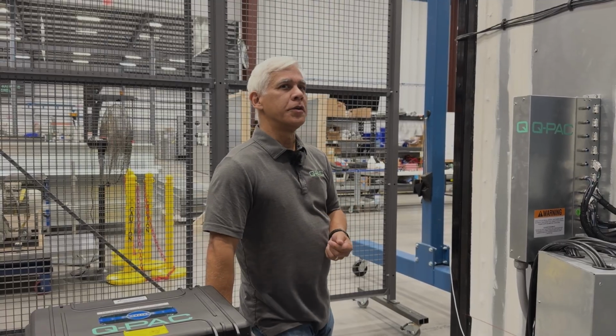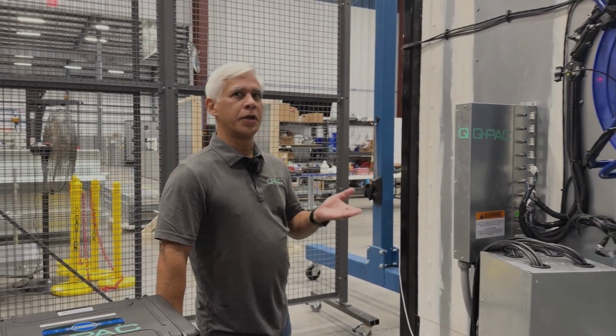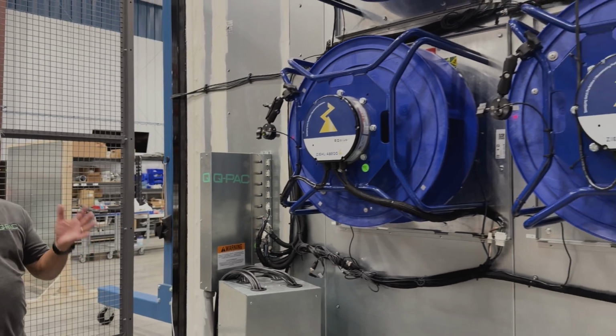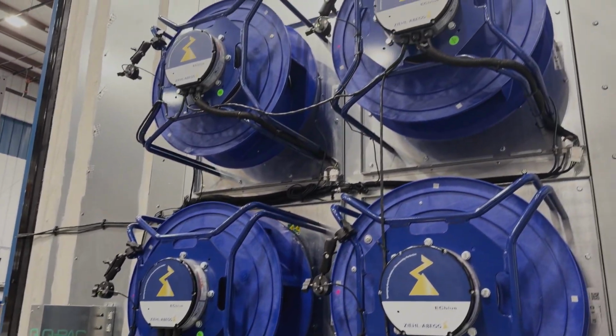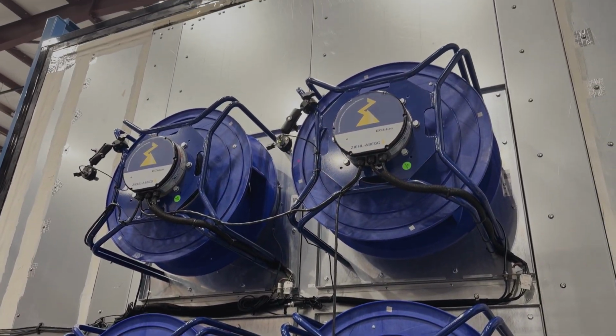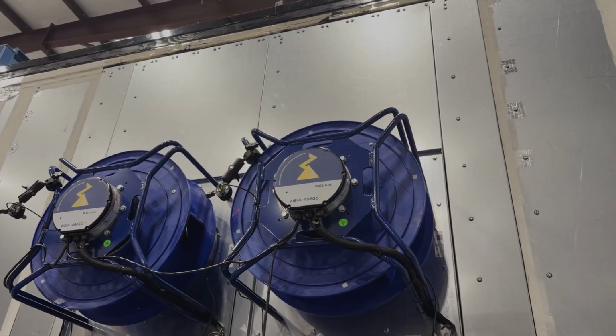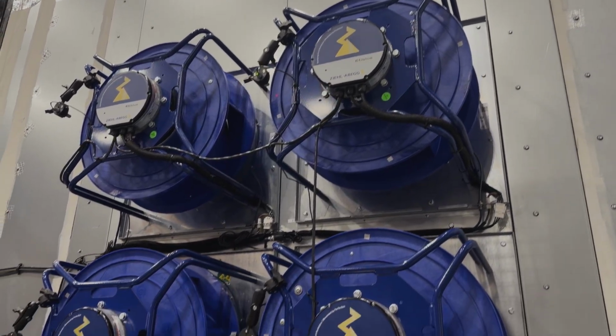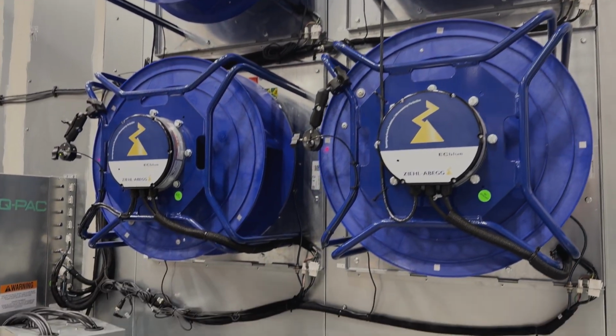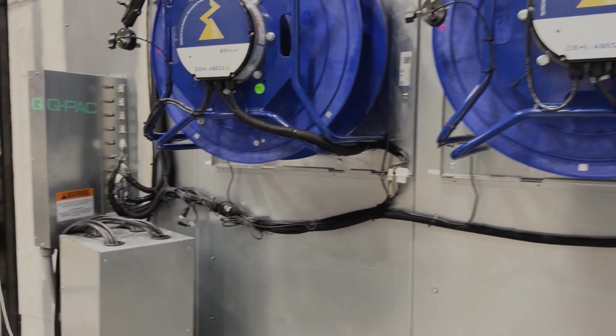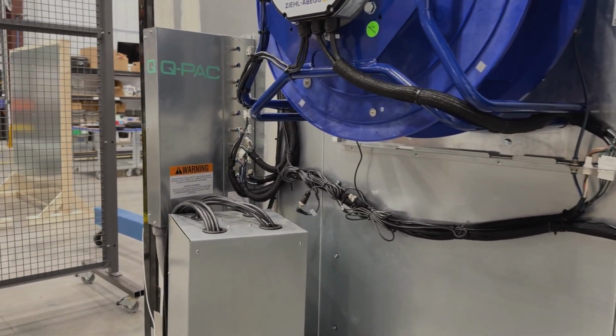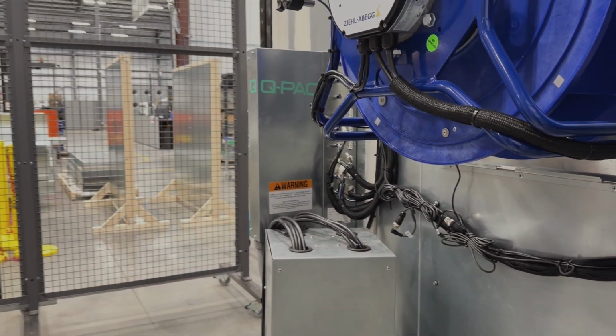But there are other things we can do besides just varying the voltage straight up. We can vary voltage in different phases. Most of our motors are 3-phase motors. So we can see the impact of losing an entire phase and maybe make some mitigation strategies. We can look at the effects of injecting harmonics, removing harmonics. And all those things are things we can characterize and measure with the equipment we have here.